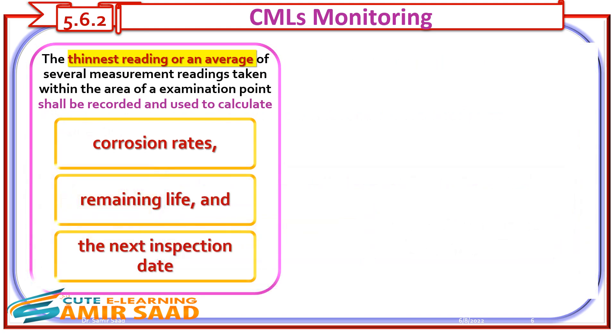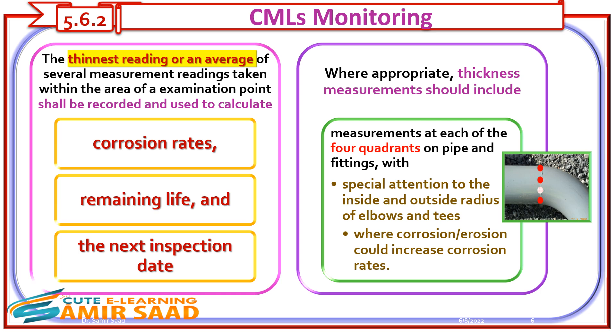The thinnest reading, or an average of several measurement readings taken within the area of an examination point, shall be recorded and used to calculate corrosion rates, remaining life, and the next inspection date. Where appropriate, thickness measurements should include measurements at each of the four quadrants on pipe and fittings, with special attention to the inside and outside radius of elbows and tees where corrosion or erosion could increase corrosion rates.